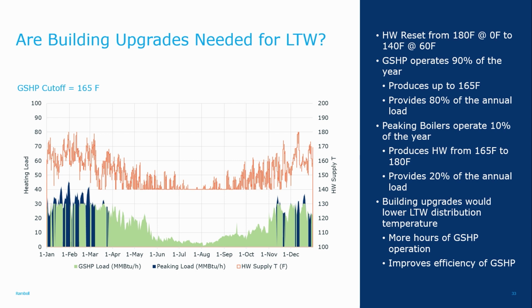They don't necessarily need to change all their coils to 140 degrees. They can get by with their existing equipment until they get to those renovations, because it doesn't pay back to do that upfront and include that cost into your heat pump plant. It improves efficiency, and we want that to happen over time, but it's not necessary to start the transition.